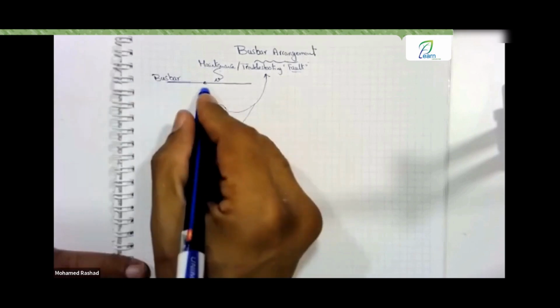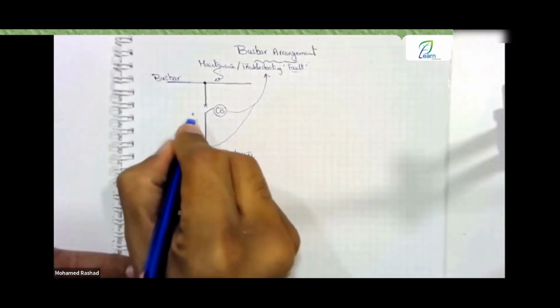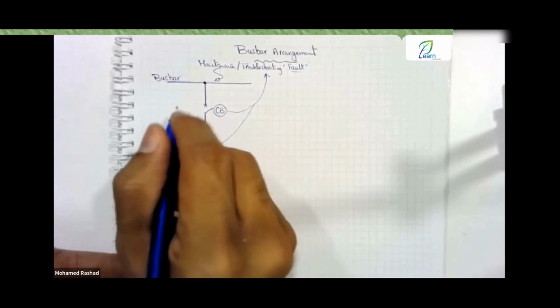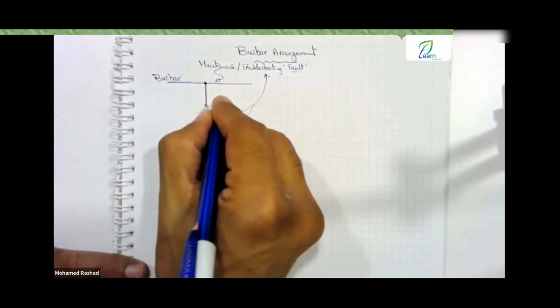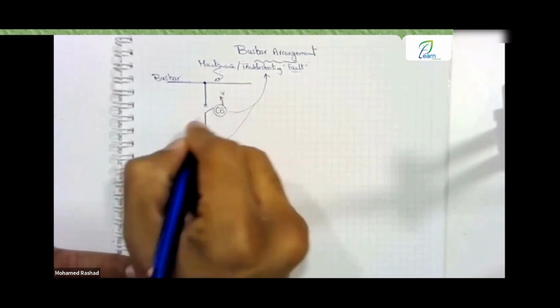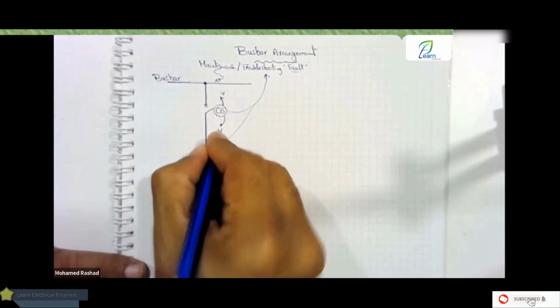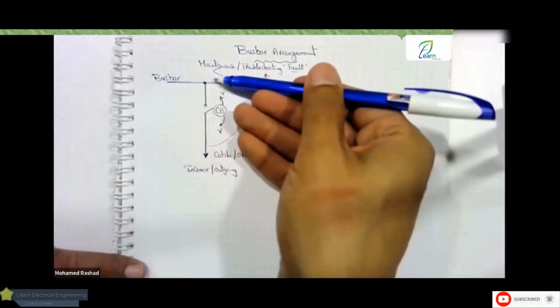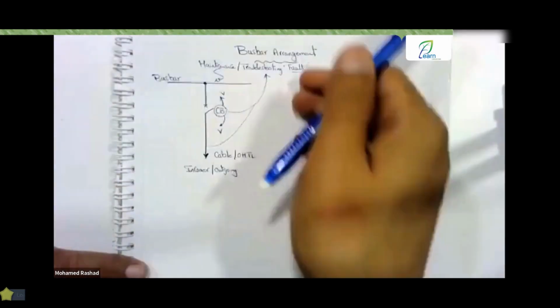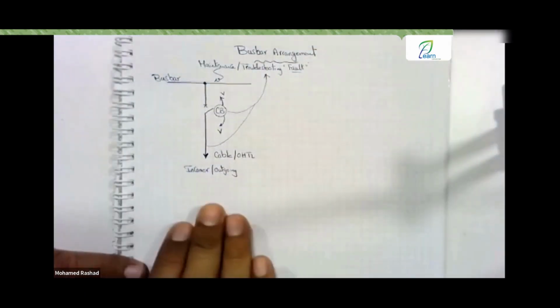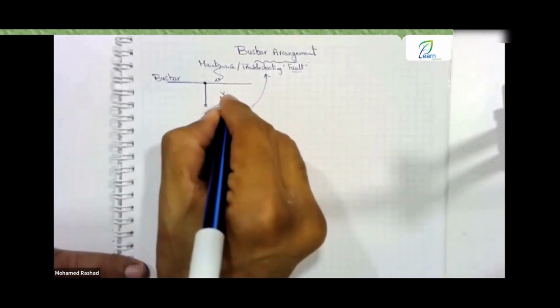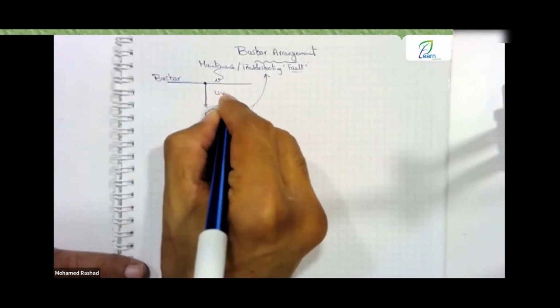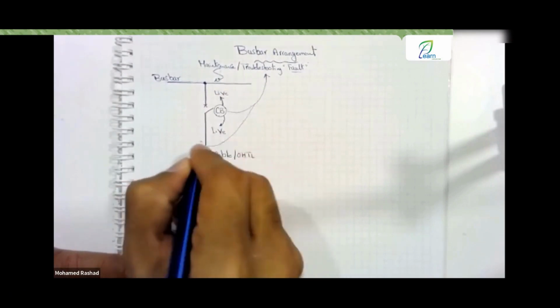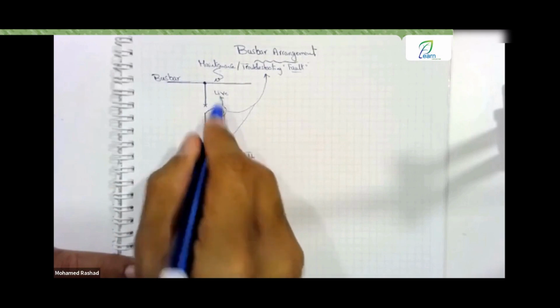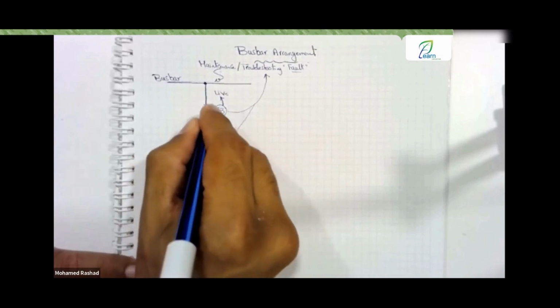When it comes to the electrical component, you want to perform maintenance on it or troubleshoot it. This terminal has voltage on it, and the other terminal's cable might have a load, meaning this bus bar could be receiving from an incomer and supplying your load, or what is coming here could be your supply feeding the bus bar. So either this side or that side will be live. That's why I wrote the letter V and left it as live. Consequently, because both are live, or one of them is live, you can't work on this setup.